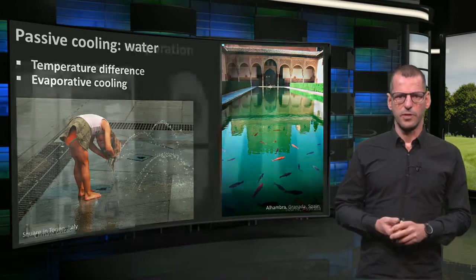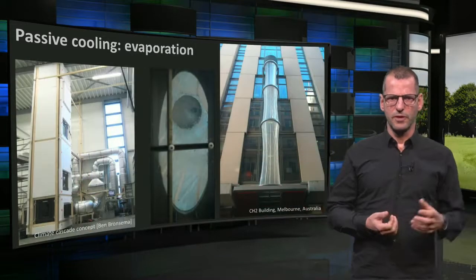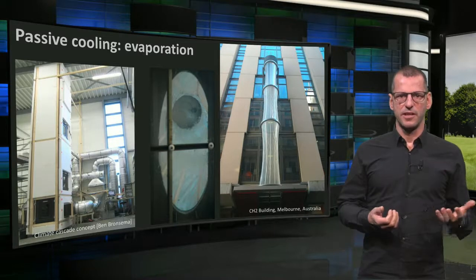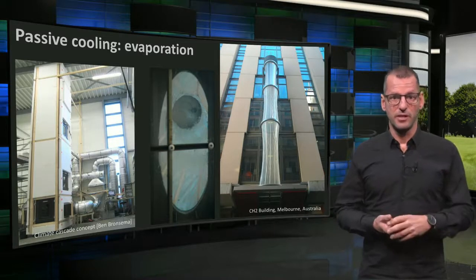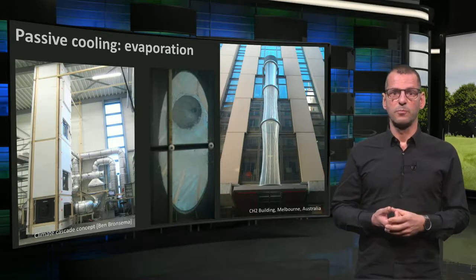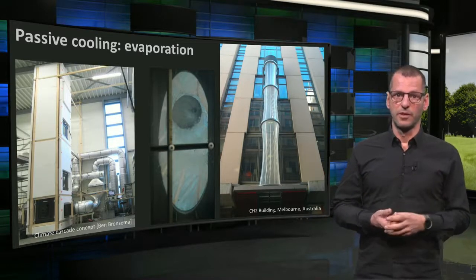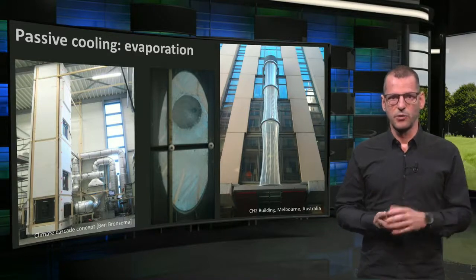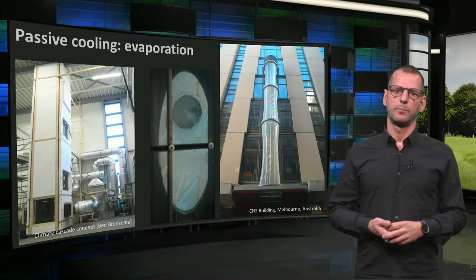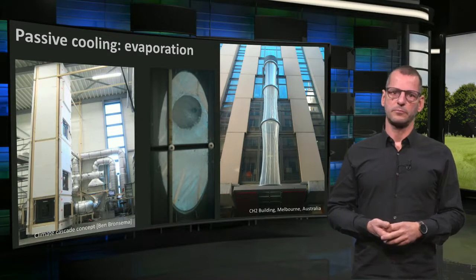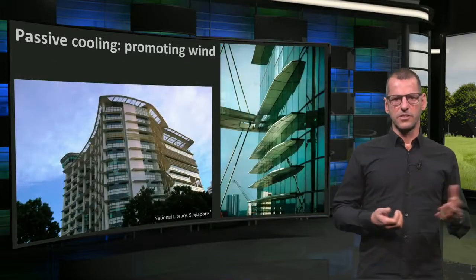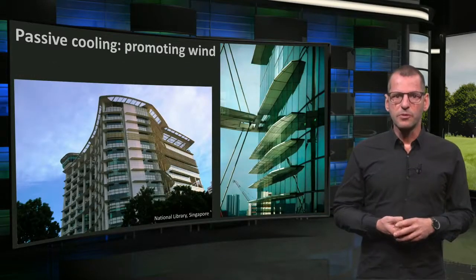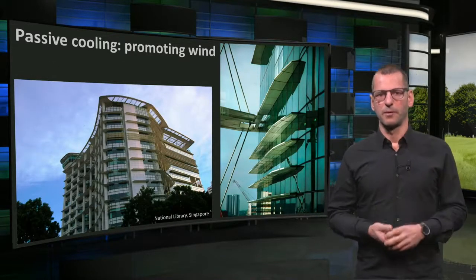This principle can be used to cool down air coming into buildings. Fresh air is then let in through an air channel in which water droplets are falling, evaporating by the warm incoming air and hence cooling it on the way. In humid climates, such as a tropical climate, the principle of evaporative cooling works less well.